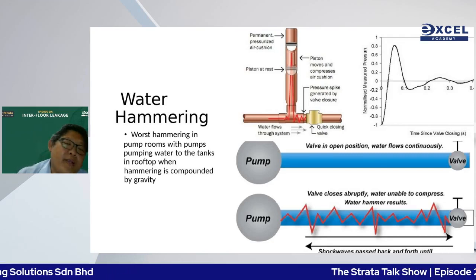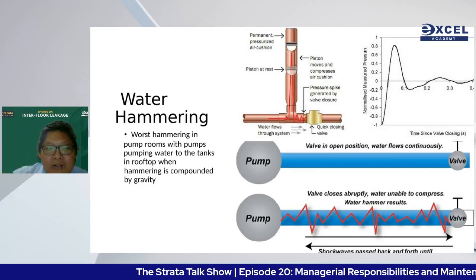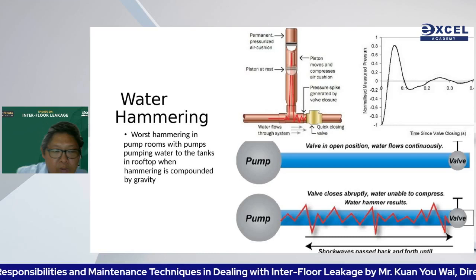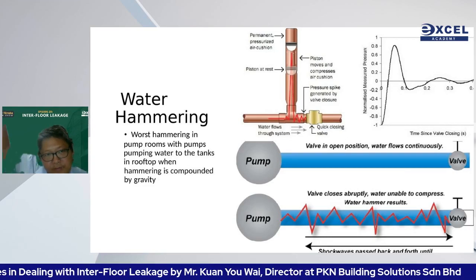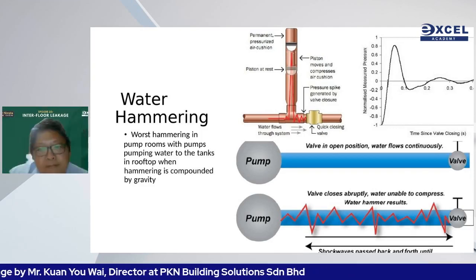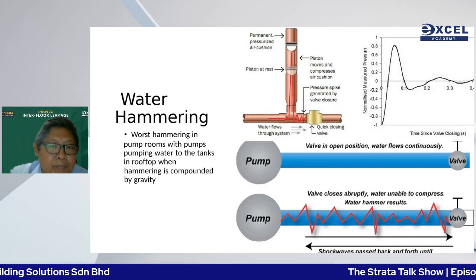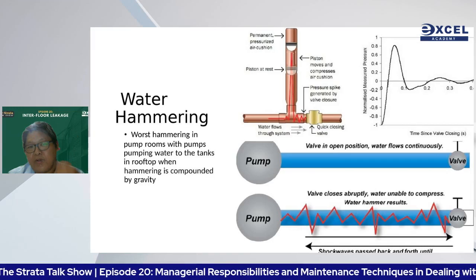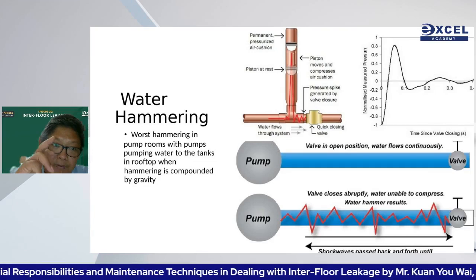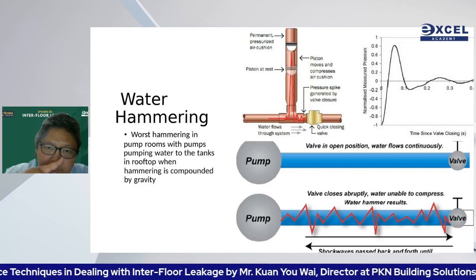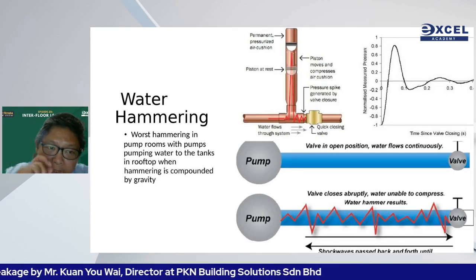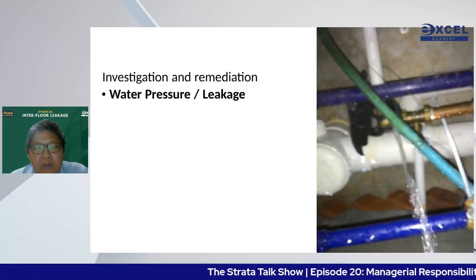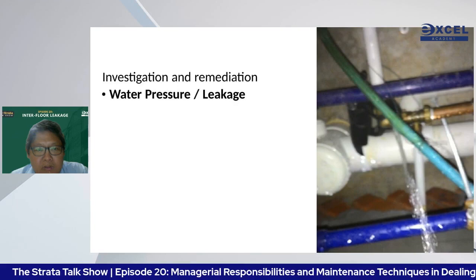Water hammering sound, especially in the pump room, occurs when the pump stops and water pushes back due to gravity, banging the pipes. This hammering can be as heavy as 600 pounds of force on the pipe, eventually causing a burst. A water hammer arrestor — containing a piston and air layer — absorbs the pressure surge when triggered.